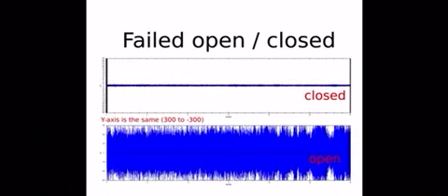How about a dynamic signal taken on a steam trap that has failed closed? Look at the y-axis scale. There's not really a lot of signal here. The temperature is cold, so the trap has failed closed, or there's a blockage somewhere.